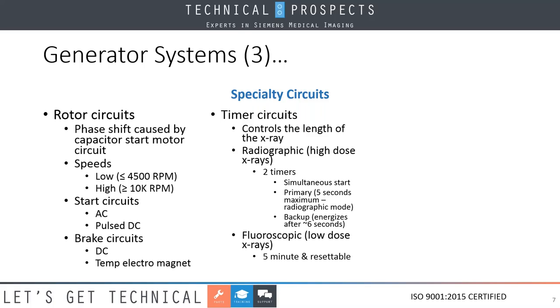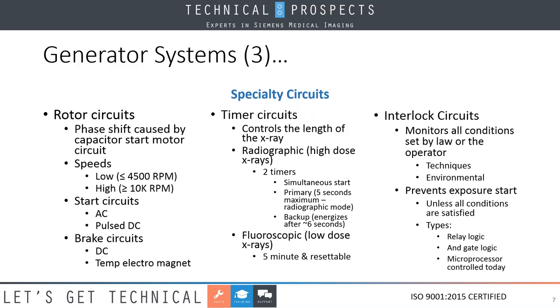And when it does, it puts flashing signs all over your X-ray machine to let us know that it decided to work and that we have a problem. On the fluoroscopic side, which is low dose X-rays, we usually have a 5 minute timer, and this is also resettable. Our last specialty circuit that we're going to talk about is the interlock circuit. This monitors all conditions set by law or the operator. Now, I like to break this down into two separate things. One is what I call techniques, and the other is what I call environmental. The techniques determine, are we going to be in either automatic mode or are we going to be in a manual mode? The environmental mode is what conditions are being set around the different environments, what signals are required, etc. regarding the starting of the X-ray.